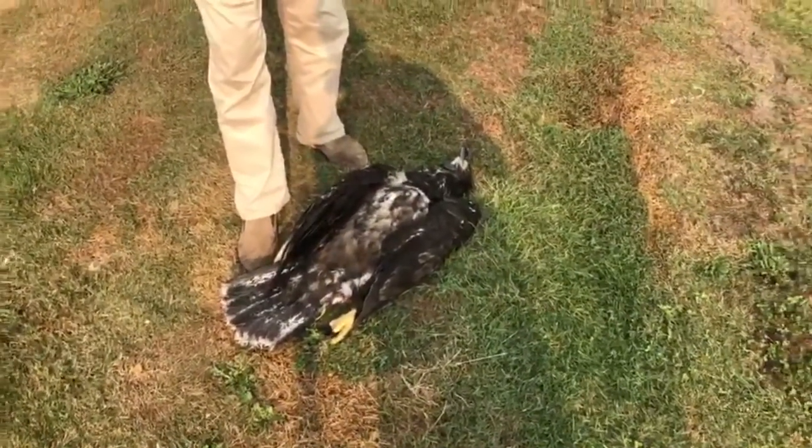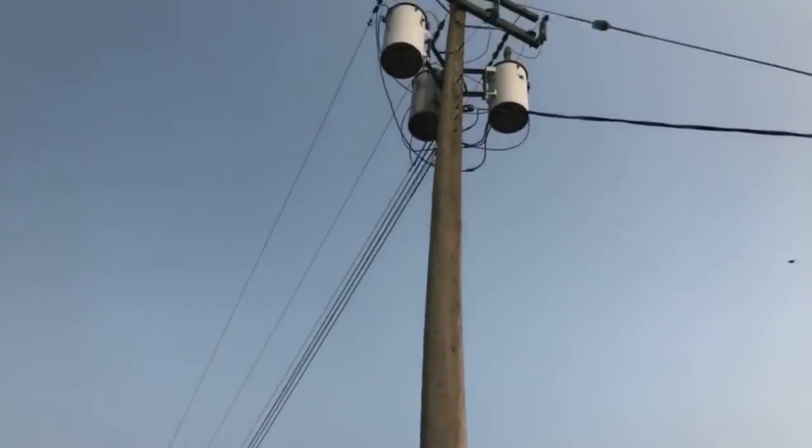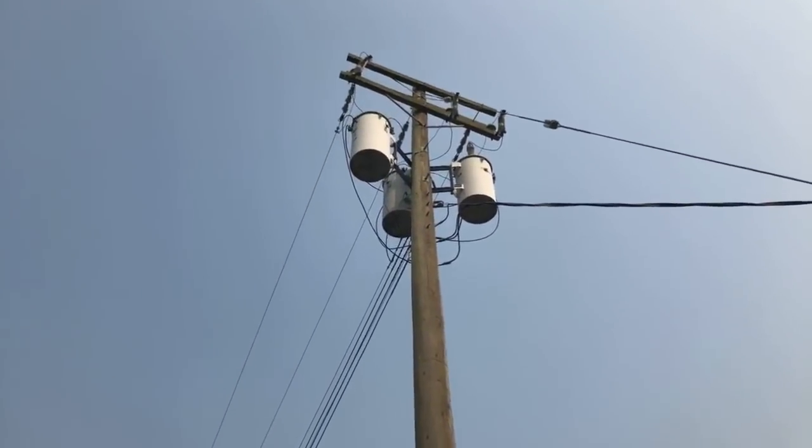Was this preventable? The answer is absolutely yes. The issue comes from two sides. What you see is three transformers — three phases coming in. You can see three lines, and if you look carefully up, you can see three phases. The phase-to-phase distance is usually smaller than the wingspan of the eagle. As David already pointed out, the problem is when they take off, their wingspan stretches right over the two phases.